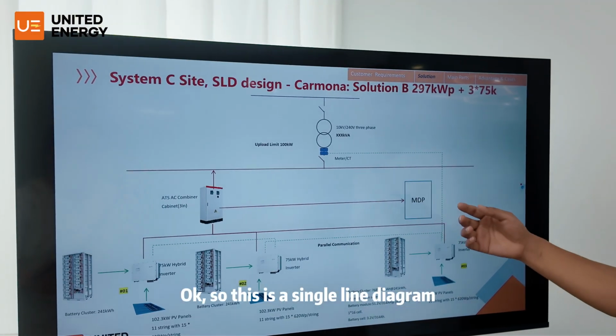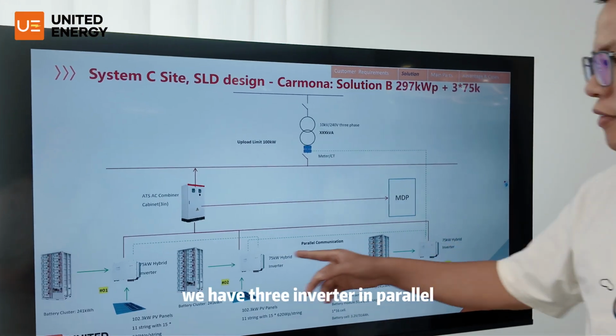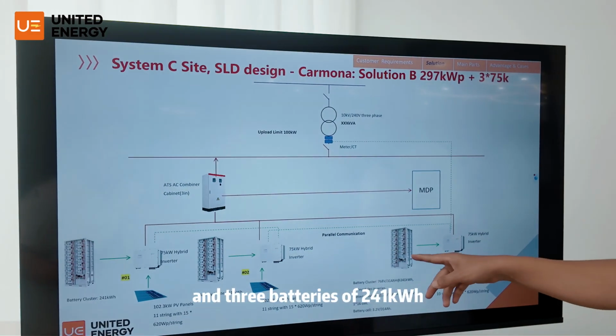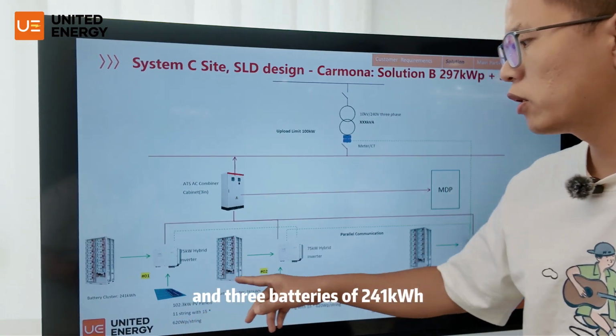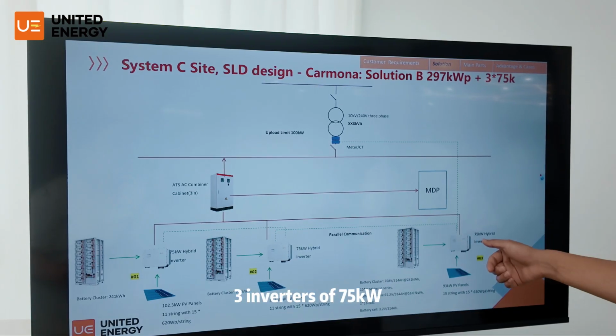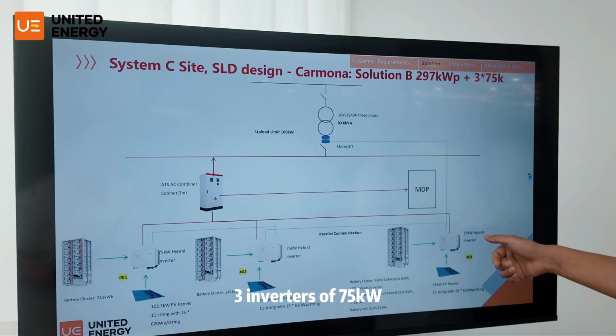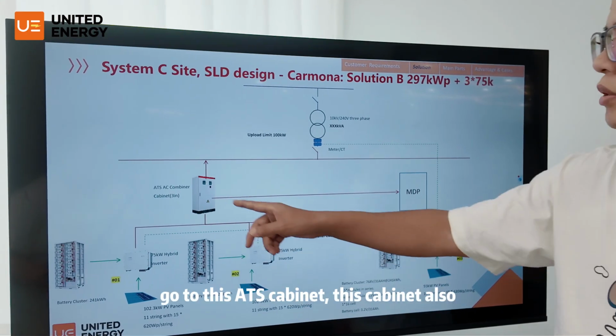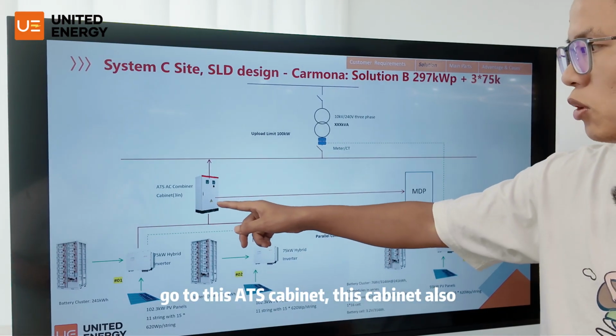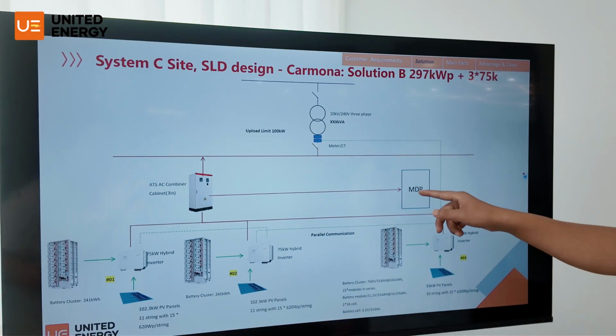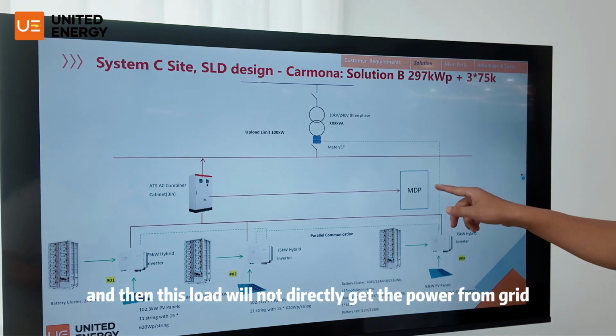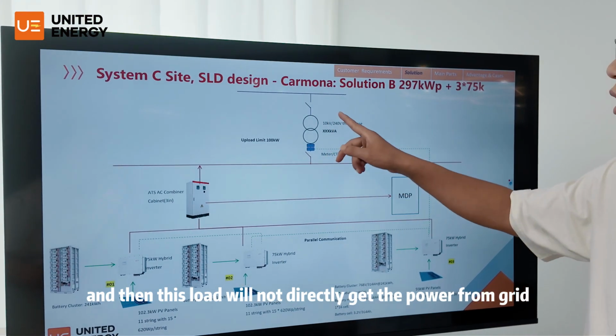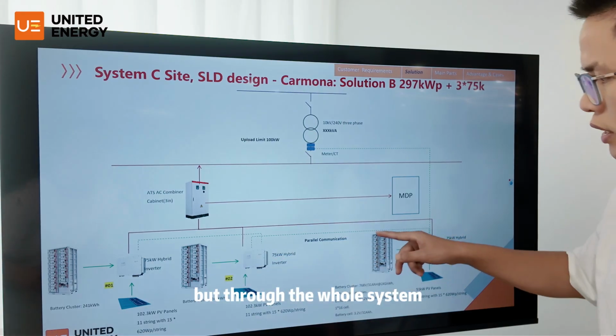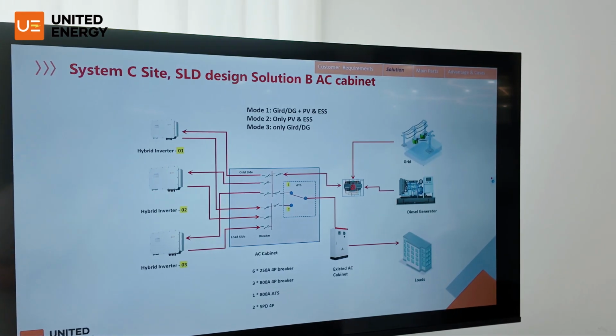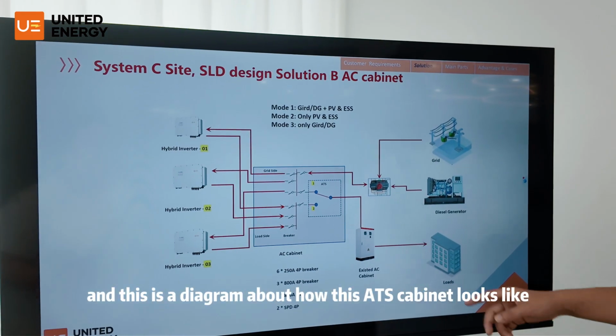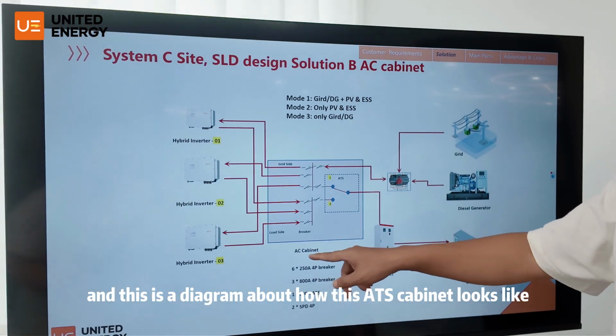Okay, so say this is a single line diagram. We have 3 inverters of 75 kilowatt in parallel and 3 batteries of 241 kilowatt hour. And they go together to this ATS cabinet. This cabinet also will go to the main load. And then this load will not directly get the power from grid, but through the whole system. And this is a diagram of how this ATS cabinet looks.